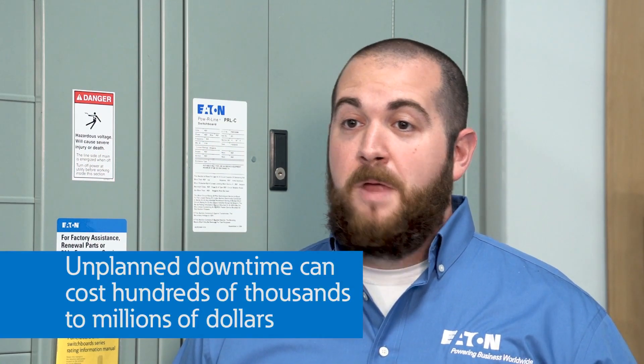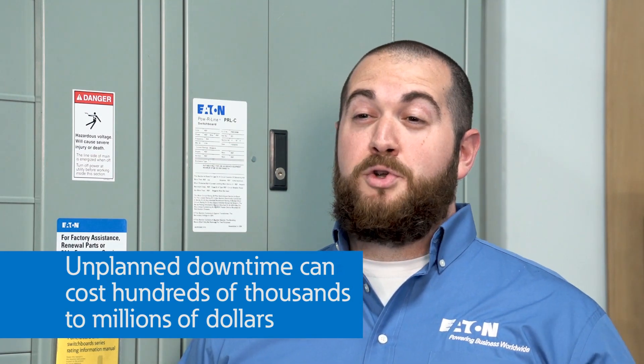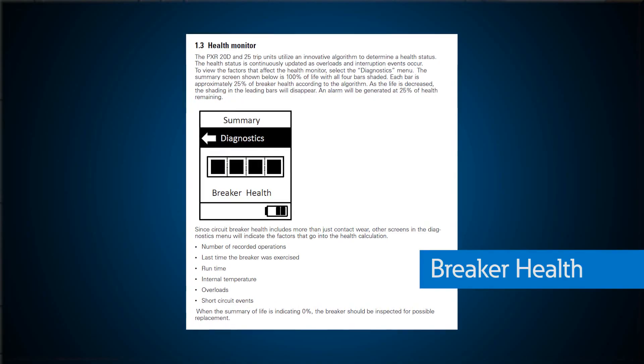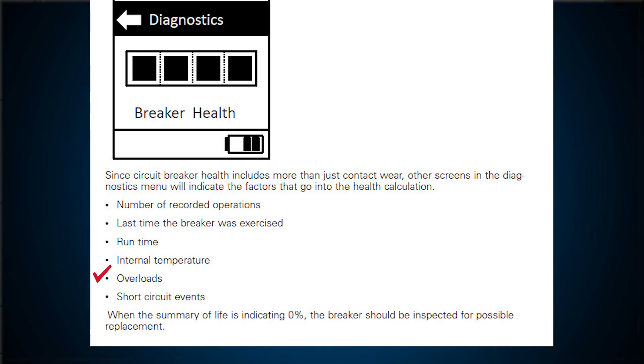Unplanned downtime for users like online tech companies, manufacturing plants, or wastewater treatment facilities could cost them anywhere from hundreds of thousands to millions of dollars and present safety issues. The good news is that Eaton is full of experts that have analyzed how differing conditions affect molded case circuit breakers over time for several years. Power Defense molded case circuit breakers with PXR trip units offer a unique feature called breaker health. Breaker health empowers the trip unit to monitor conditions that affect the health of the breaker, such as overload events, short circuit events, breaker operations, or how many times the breaker is turned on and off, when the last operation took place, how long the breaker has been in service, and the internal temperature of the breaker. All of these metrics are combined with a proprietary algorithm to provide a metric showing the health of the breaker.